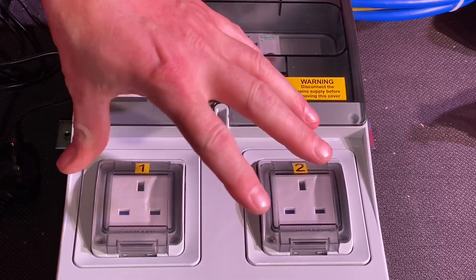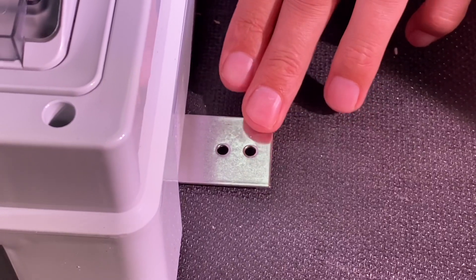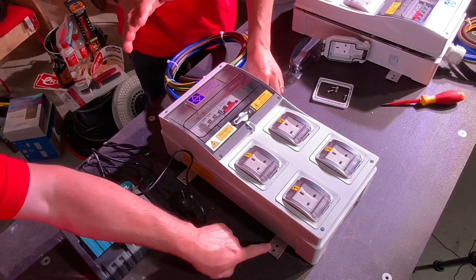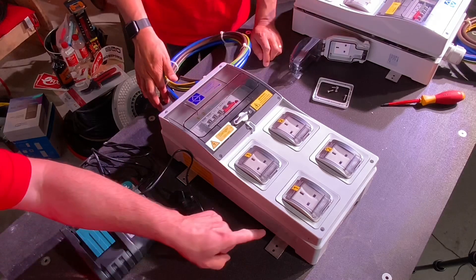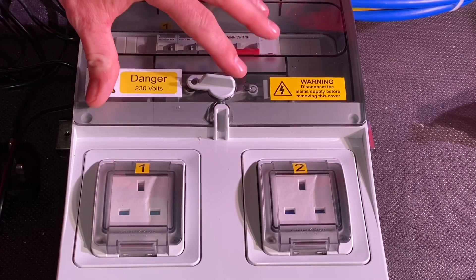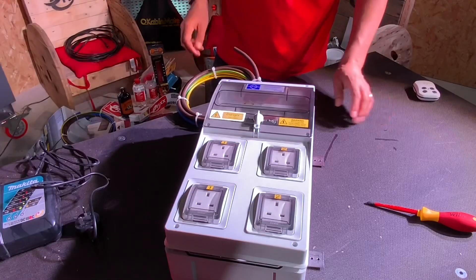There's a set of tails at the top and some internal components to look at - you wouldn't need to go inside very often. One more thing before we move on: external fixing tabs. The Top Tier range has keyhole fixings on the back, but if you fix this to a bit of plywood with the screw fixing hidden behind it, whoever comes along at the end of the day will just try and wrench it off the wall or open the box to remove it. The external fixing tabs address that. Let's have a look inside, because the quality in Lewden products continues throughout the enclosure.